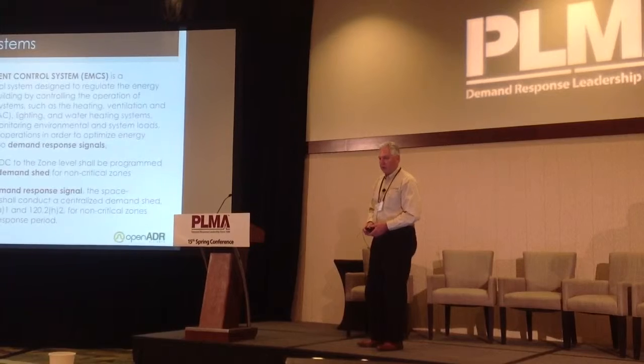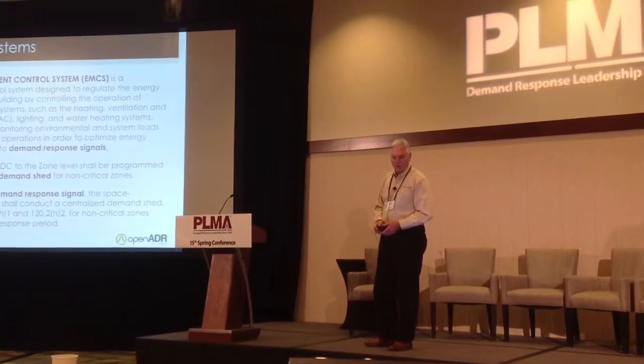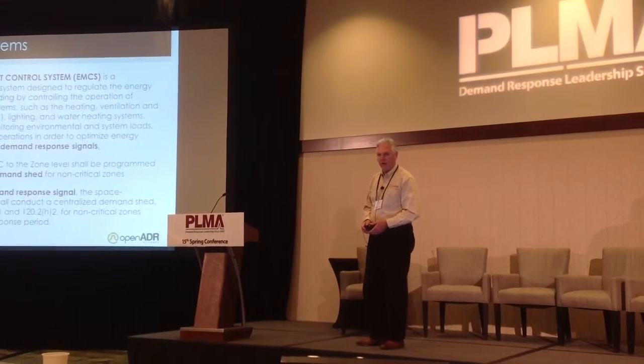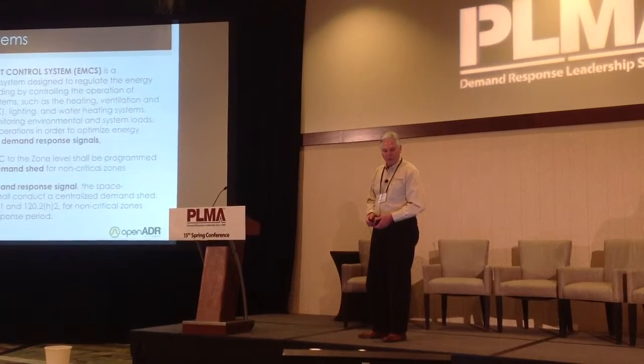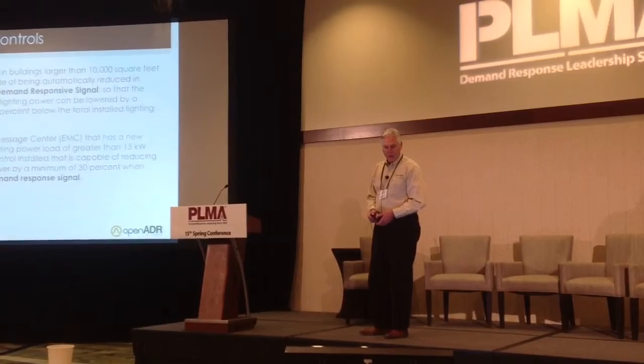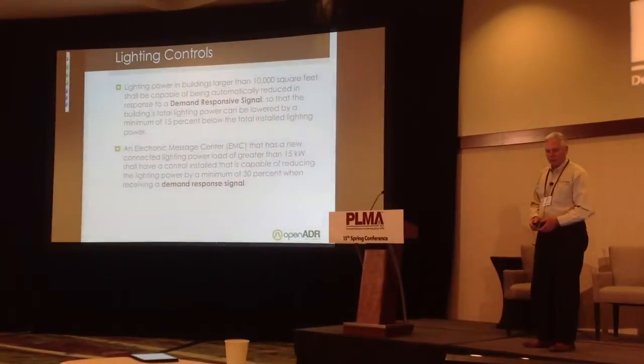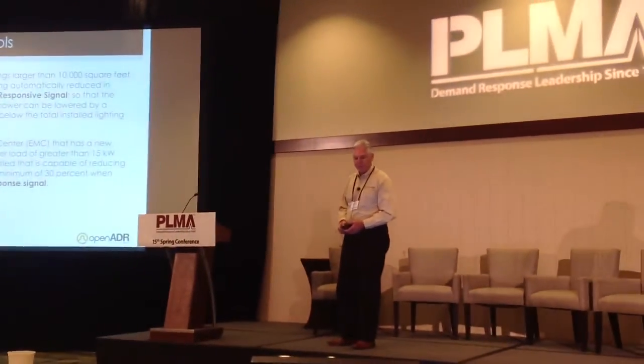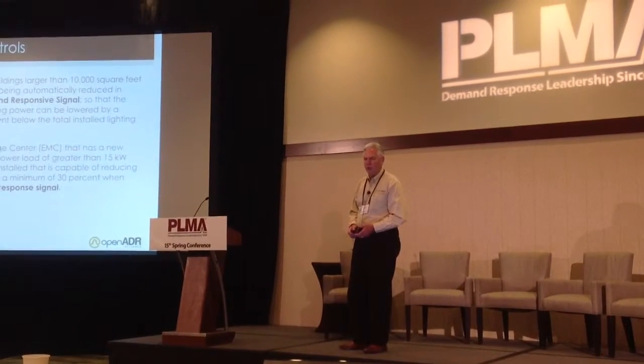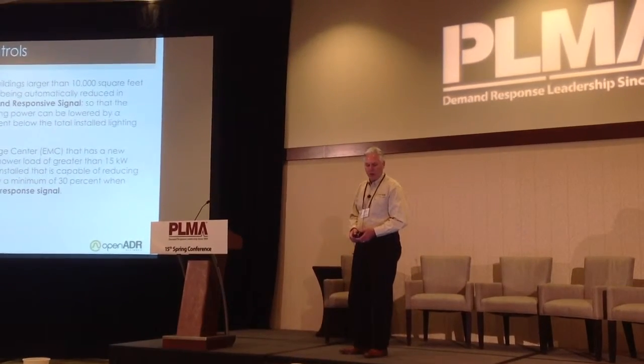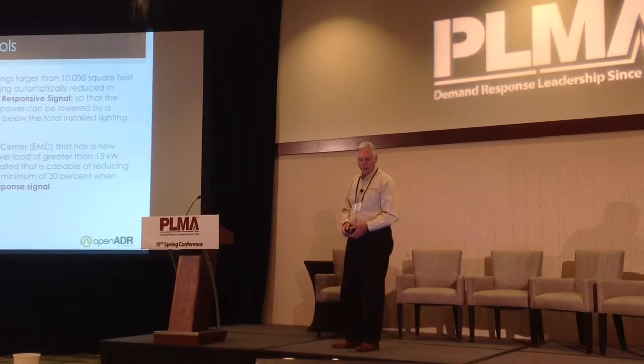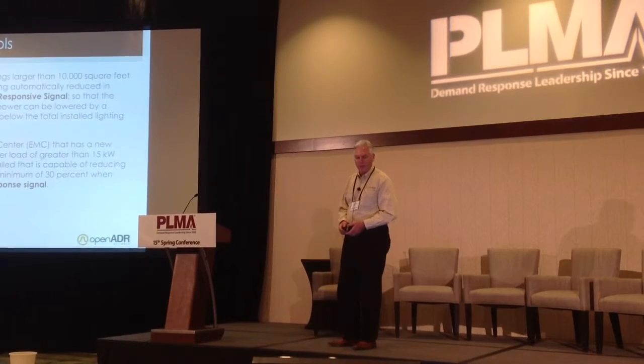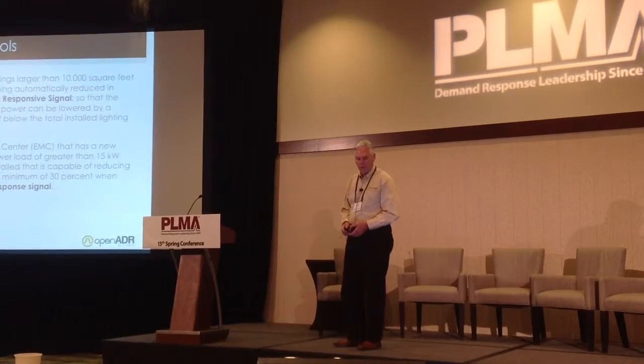There are tools being developed by the California Energy Commission to validate that systems can comply with the code. That is the reason for the delay in enforcement, which is supposed to take place on January 1st. This also impacts lighting controls — lighting control systems must be able to reduce energy by 15% or better. A validation tool is also being completed for lighting control systems.